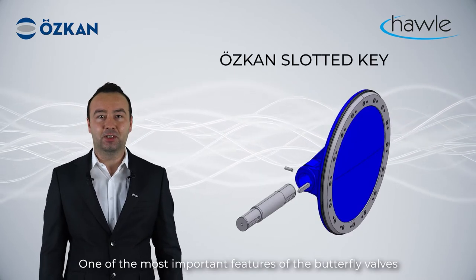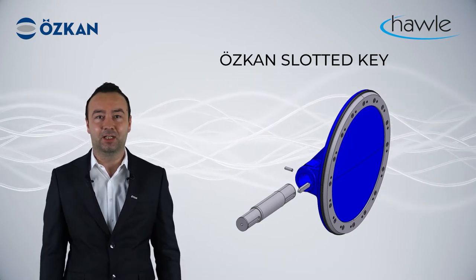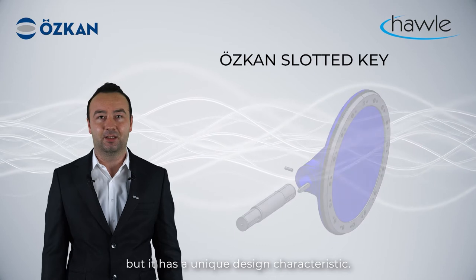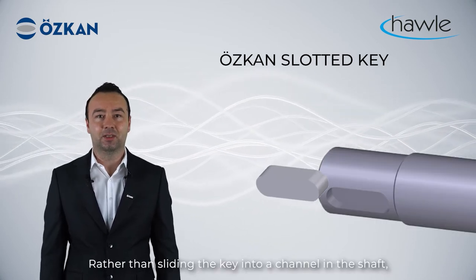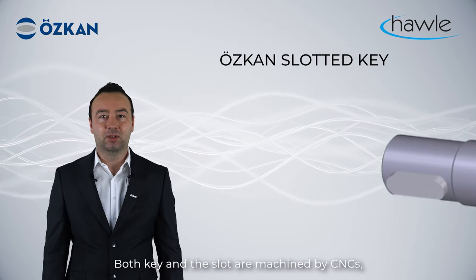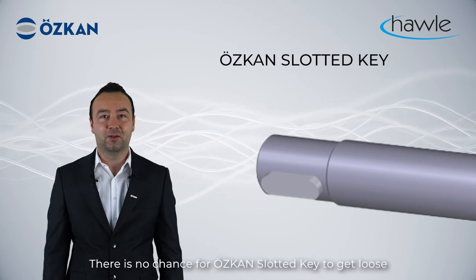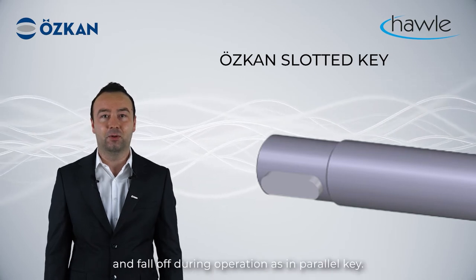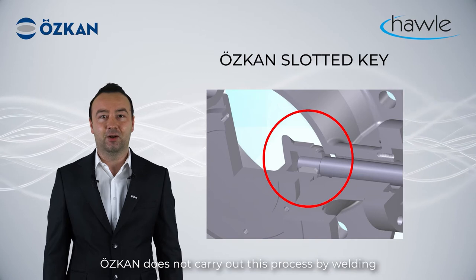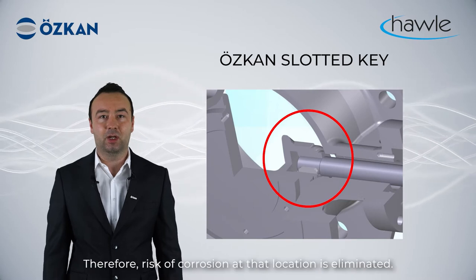One of the most important features of butterfly valves is the shaft and disc connection technology, which we named the ÖZKAN Slotted Key. At first sight it seems like a parallel shaft key connection, but it has a unique design characteristic. Rather than sliding the key into a channel in the shaft as in a parallel key, keys are inserted into a slot in the shaft. Both the key and the slots are machined by CNC to precise dimensions and tolerances. There is no chance for the key to get loose and fall off during operation as in a parallel key. In addition, the back sides of the disc hubs are closed. ÖZKAN does not carry out this process by welding, unlike many other manufacturers, so the risk of corrosion at that location is eliminated.